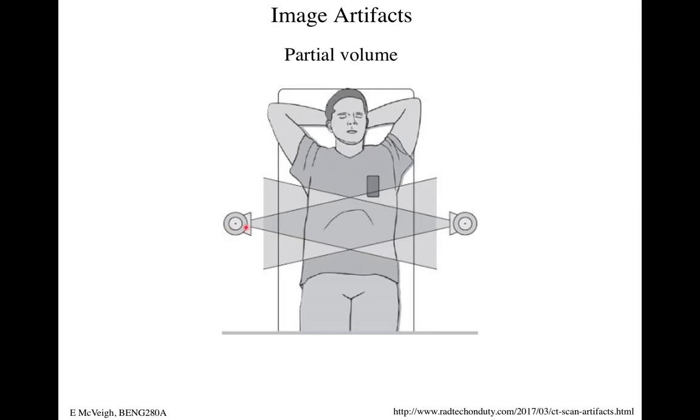However, when this thing's rotating around, you can see that in this view, these rows of the detector are seeing this tissue here. And then when it rotates around 180 degrees, they're missed, right? And so you can adequately reconstruct a kind of football-shaped thing, as opposed to a cylindrical volume. So that's taken into account when you calculate what your field of view is in this direction.